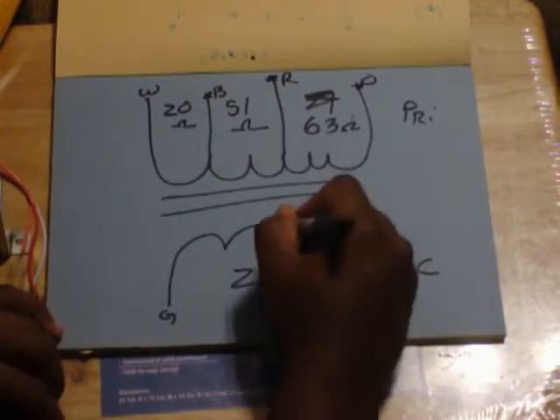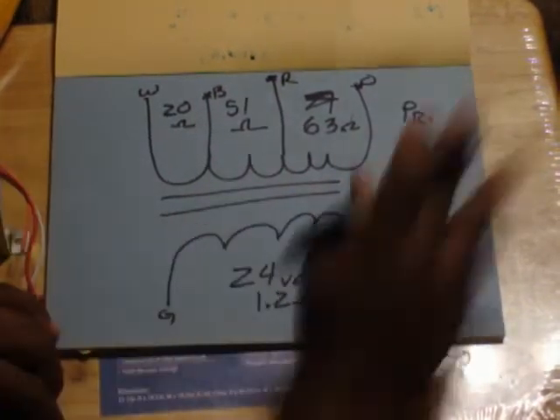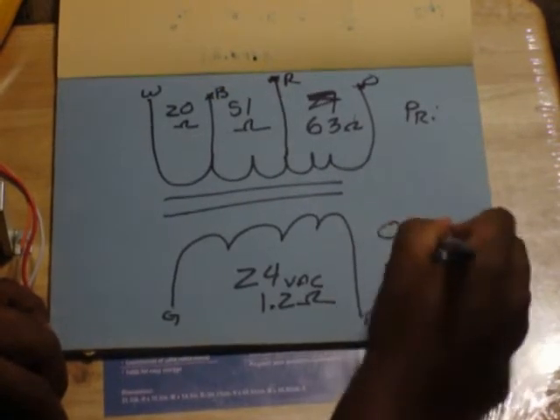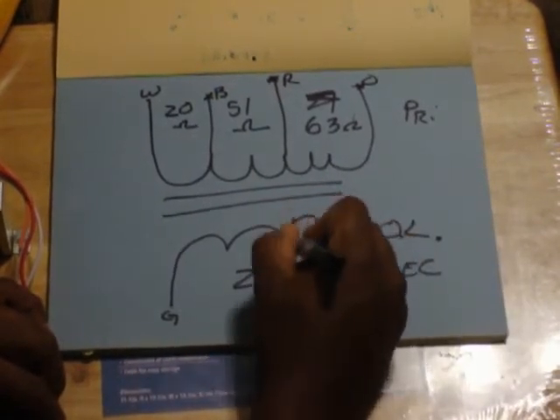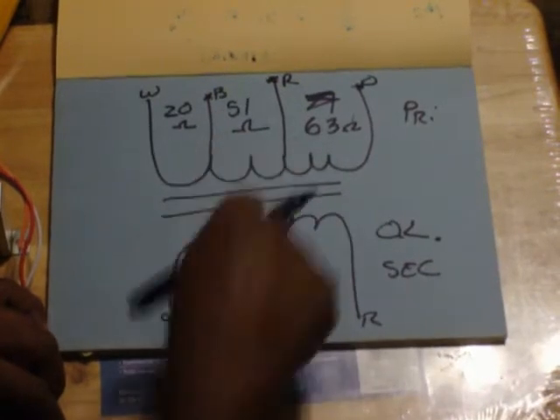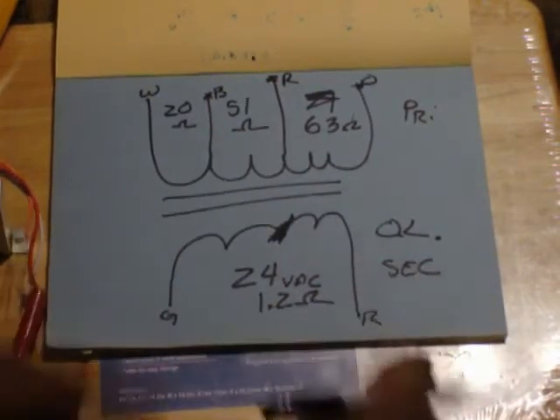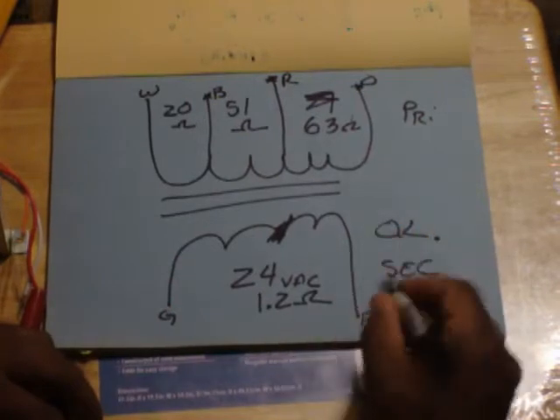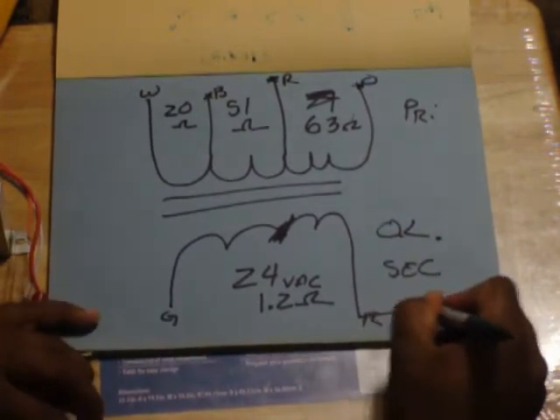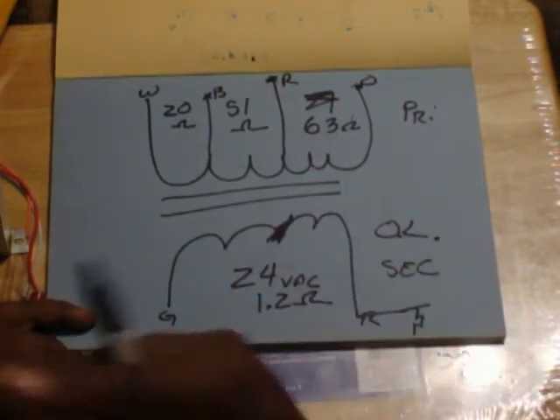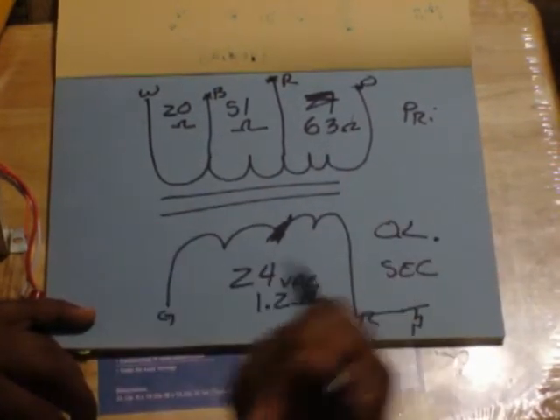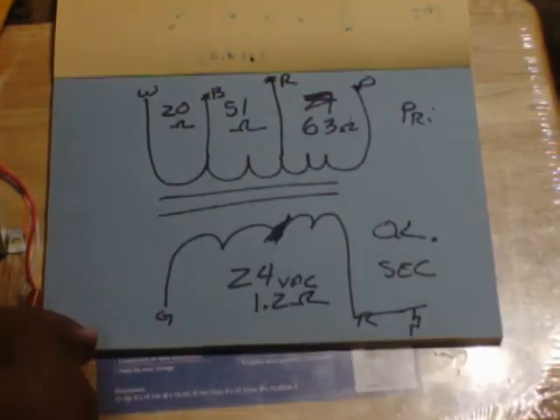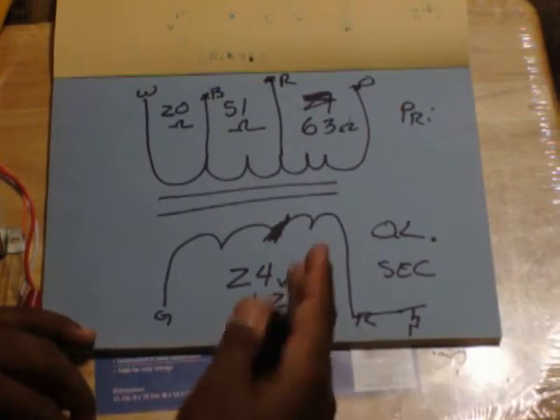But it's very simple. My caution here again, if you check from green to red or whatever your color is on yours, and this reads an open line, OL, that means your secondary was burnt out. If your secondary is burnt out, something down here, and all it feeds, goes to your thermostat, and then your thermostat feeds your blower relay on your contactor. Your blower relay is shorted out, your contactor is shorted out, one or the other, or you have some wires going to the condenser unit. I've seen dogs chew them out, rats chew them out, squirrels. Something is shorted that keeps blowing your transformer.